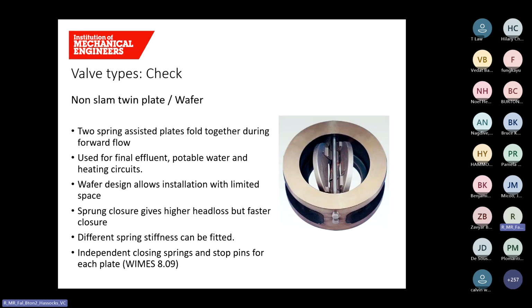The wafer check valve can be used on final effluent wastewater applications, potable water and raw water for water applications, and also on heating circuits. The design consists of two metal plates which are spring loaded, causing the valve to close very quickly once the flow stops. The main benefit of this valve is its very short flange to flange dimension, which means it can be installed where there isn't much space on a pipeline, or if a valve needs to be retrofitted to an existing pumping station.